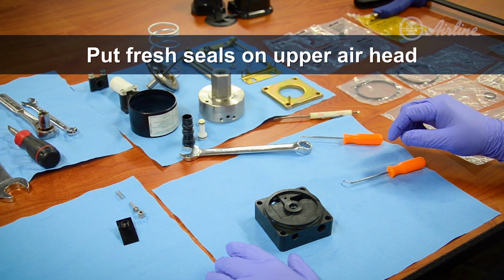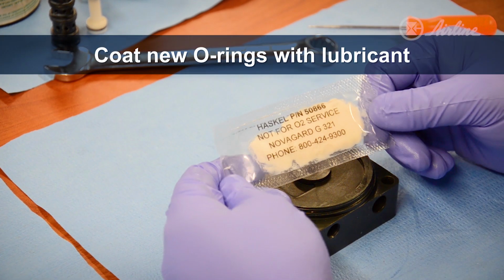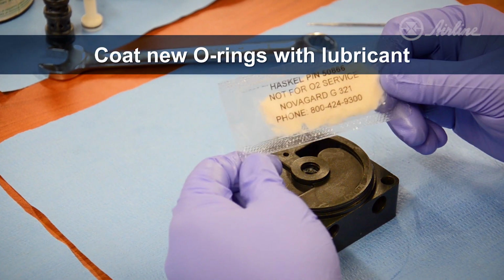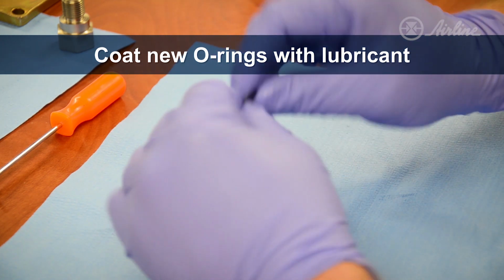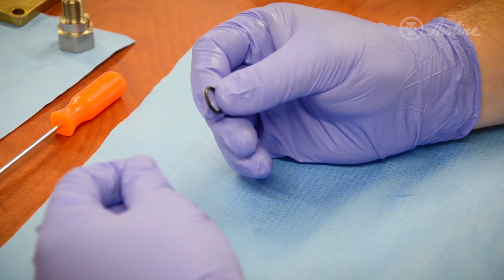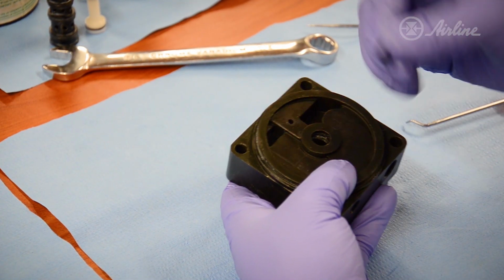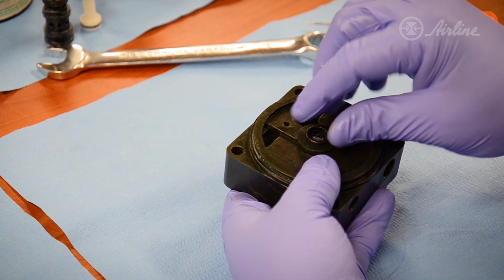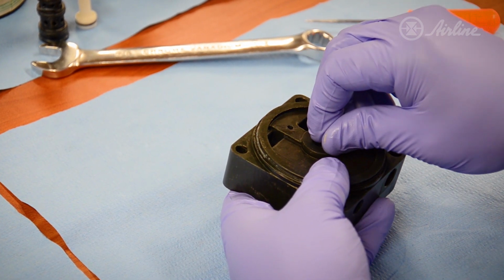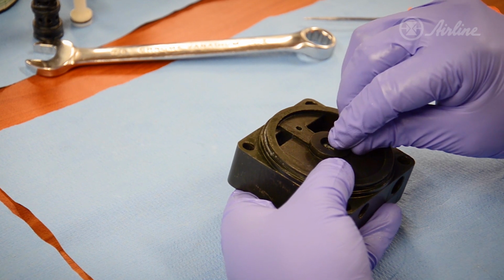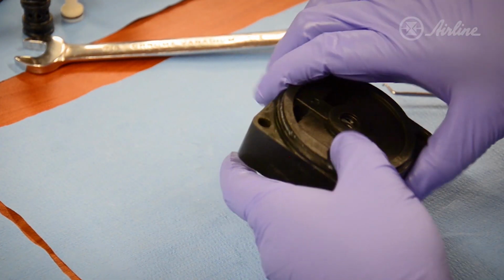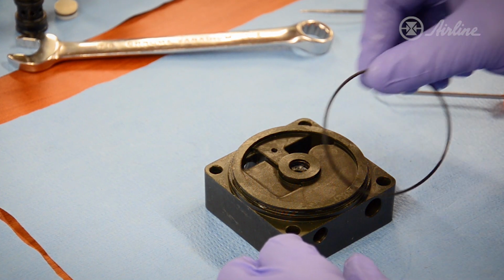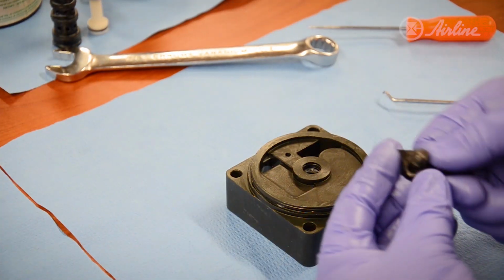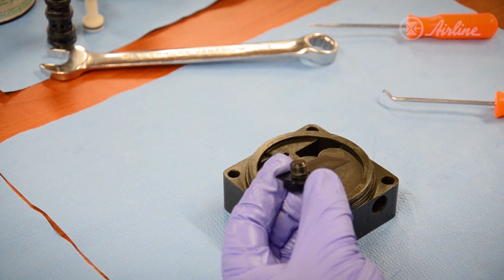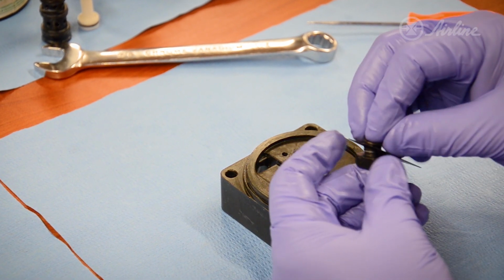So now we're going to put the fresh seals back into this upper air head. Before reinstalling any of the O-rings, use the grease supplied in your seal kit. Lightly put it on your fingers and lubricate the O-rings before reinstalling them in the pump. So first we'll reinstall this O-ring back into the head. It fits in an internal groove in here, so it has to be carefully worked in by hand and then set into place in the groove. Good. Now we'll install the outer O-ring that seals the air barrel. Now we'll install this cap O-ring, which also retains this metal plate on the unit.